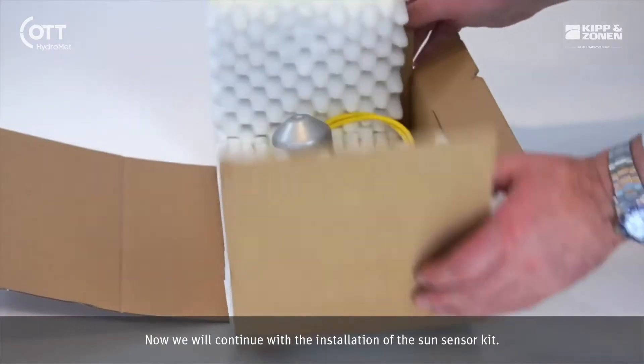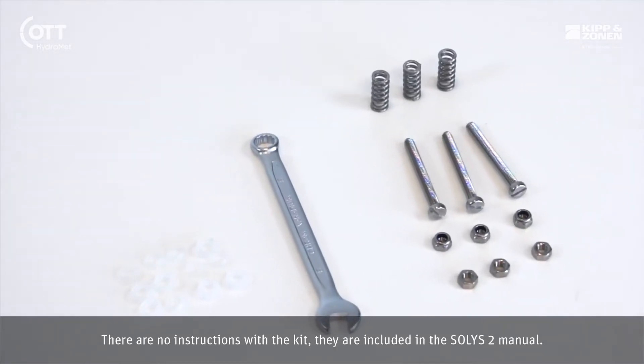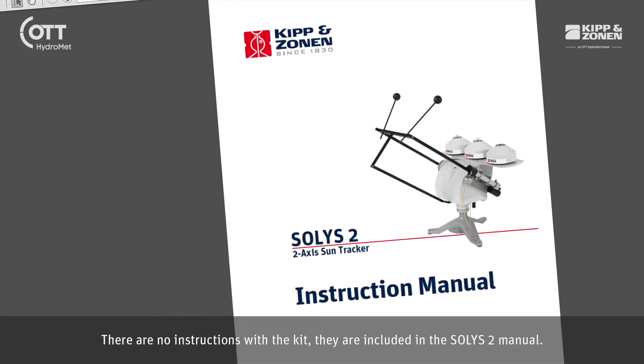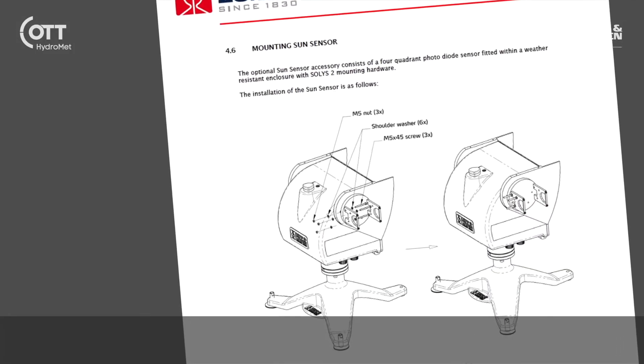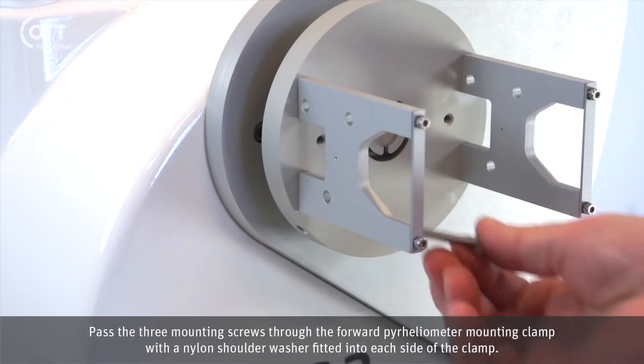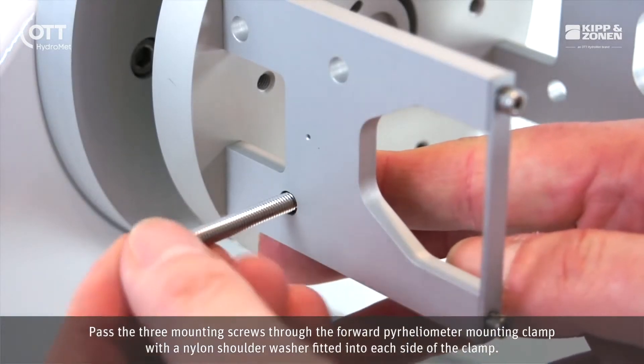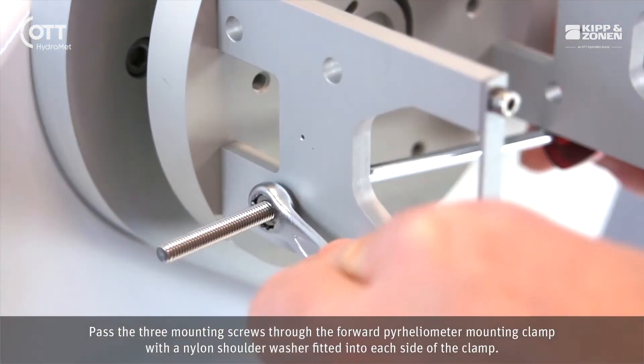Now we will continue with the installation of the Sun sensor kit. There are no instructions with the kit — they are included in the SOLYS 2 manual. Pass the three mounting screws through the forward pyrheliometer mounting clamp with a nylon shoulder washer fitted into each side of the clamp.